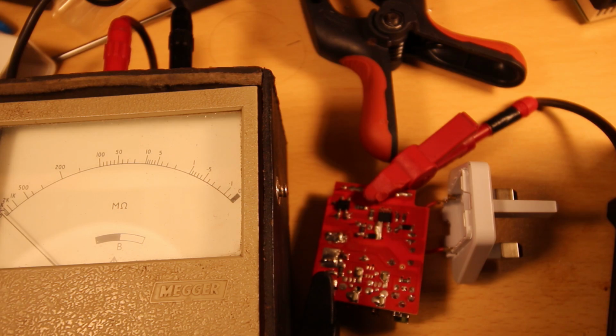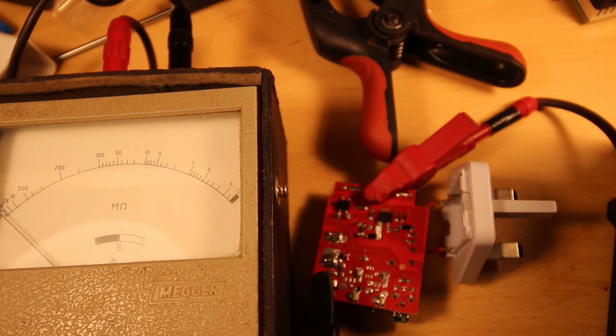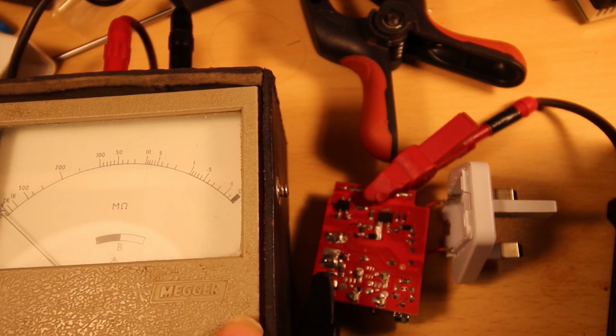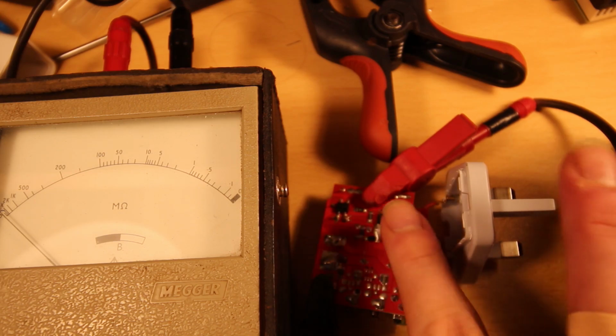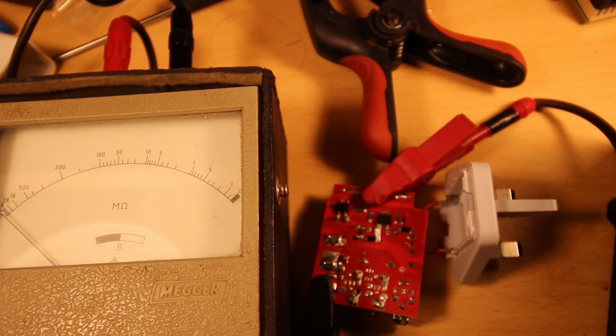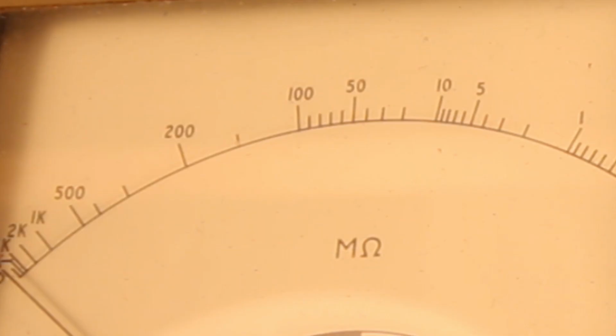Almost said a bad word then. So I have this set to 500 volts — you can't see that, but this megger is set to 500 volts. I've got it across from both output terminals to both input terminals, and the clips are shorting them out. I'm going to turn it on and we'll see what happens.